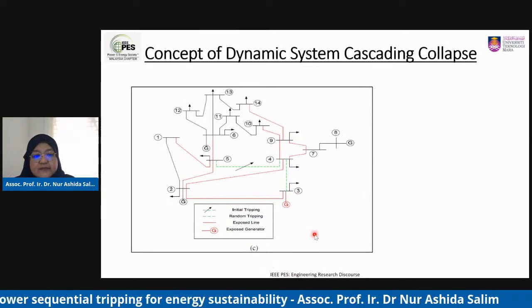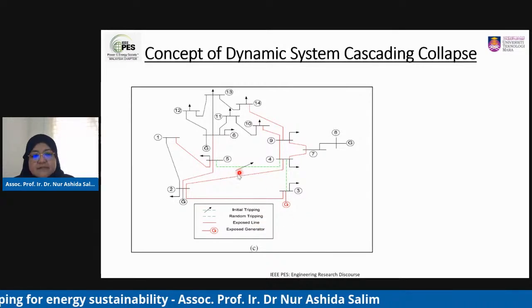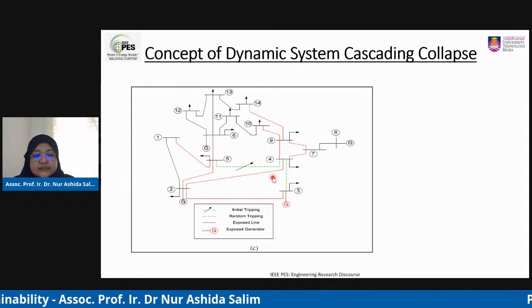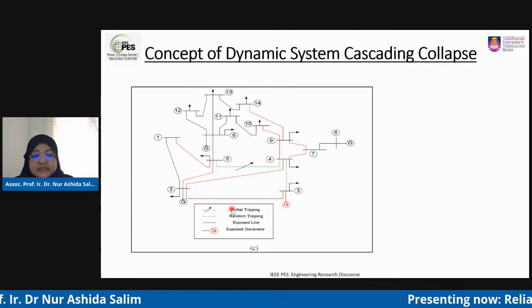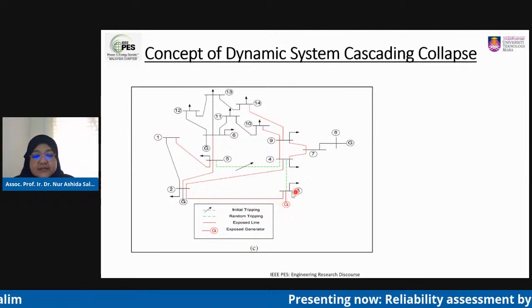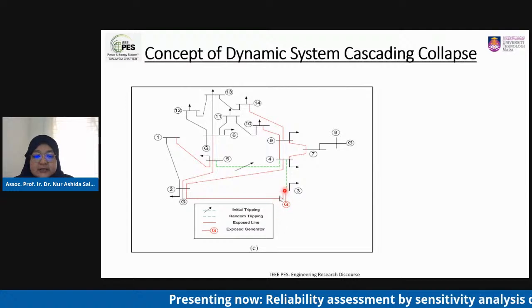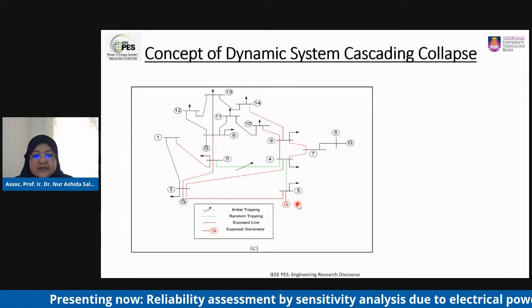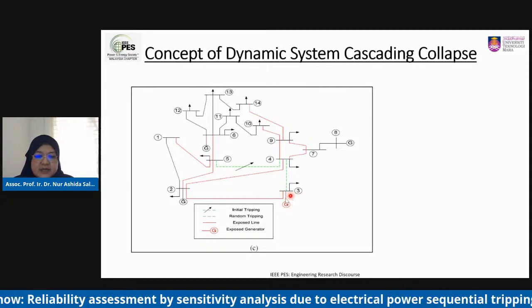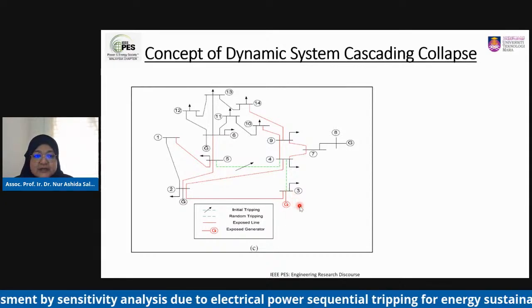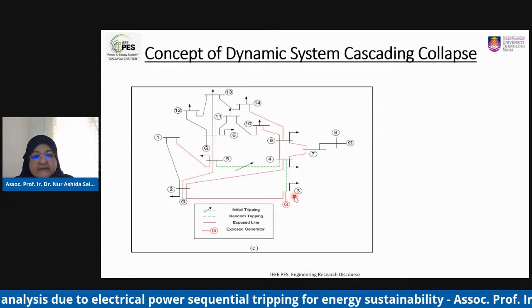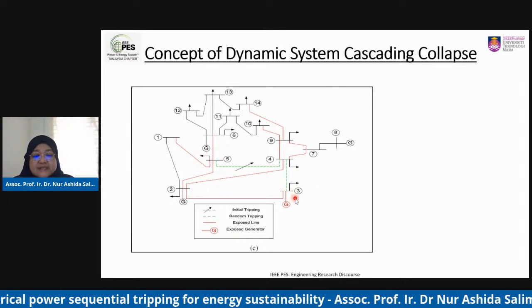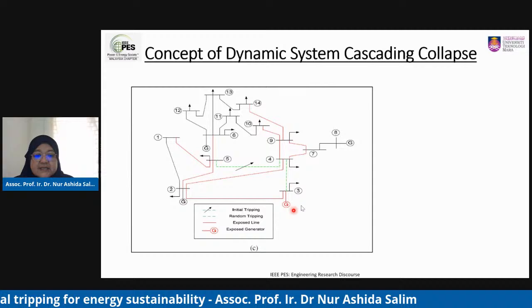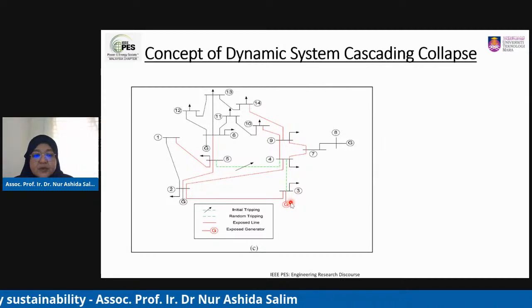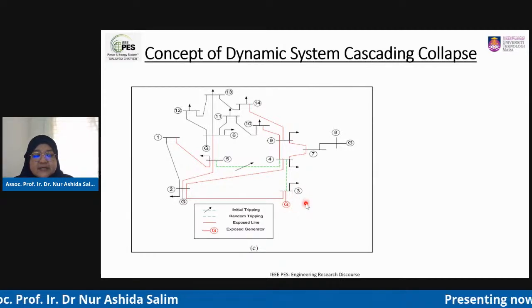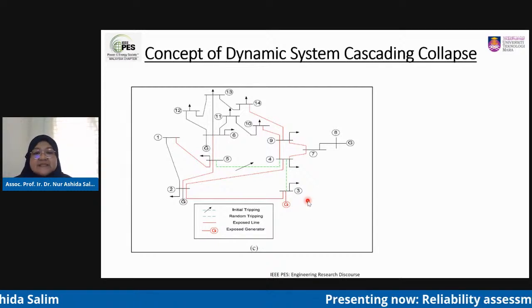All right, so we have to identify whether after power flow solution, we have looked at the thermal limit again. And for the generator, we have to identify the critical clearing time. If the critical clearing time is still within the range, this generator will still survive. But if the critical clearing time violates the limit, then this particular generator will also be disconnected from bus number 3. That is called the dynamic system cascading collapse.